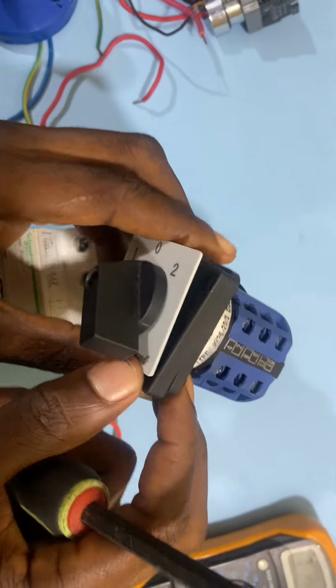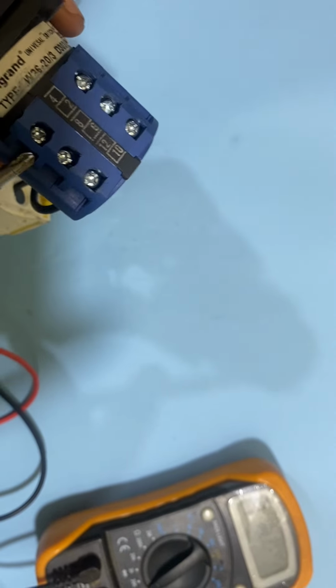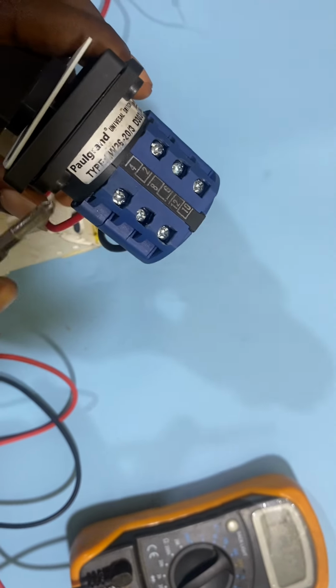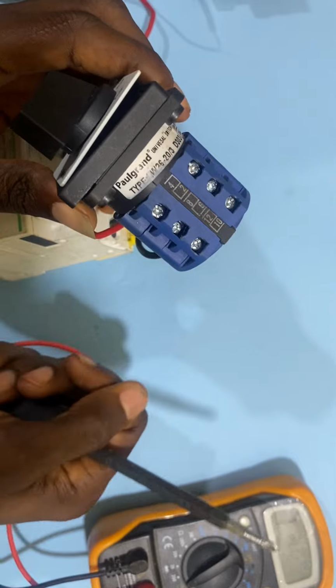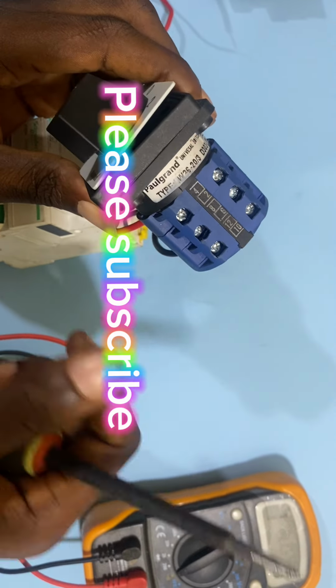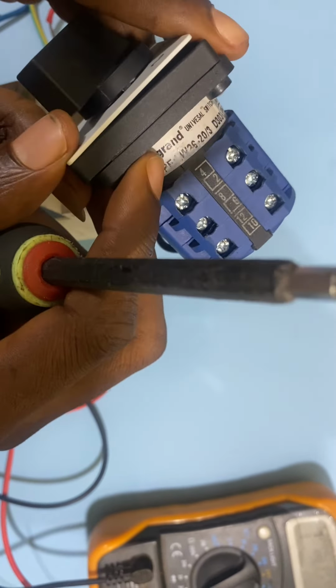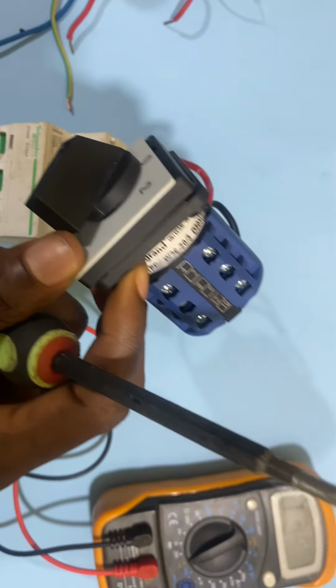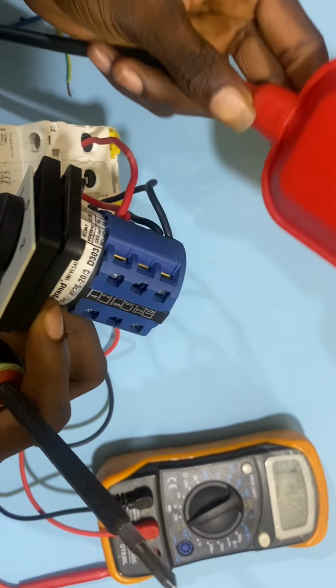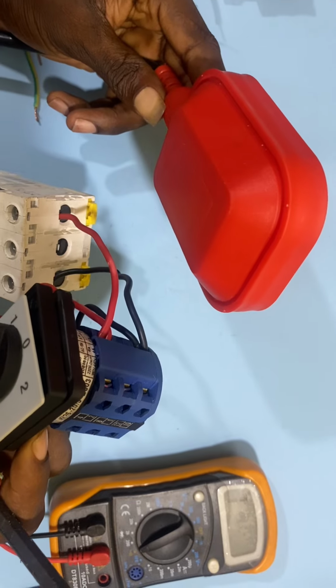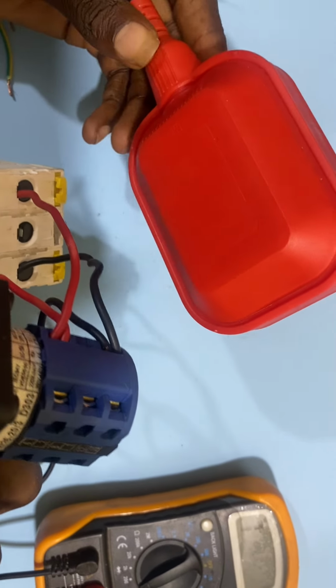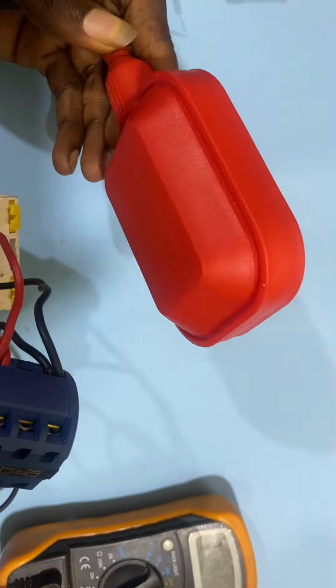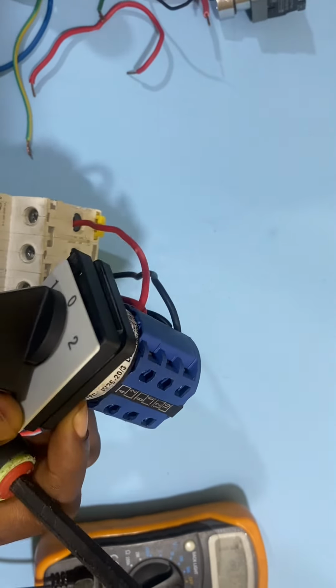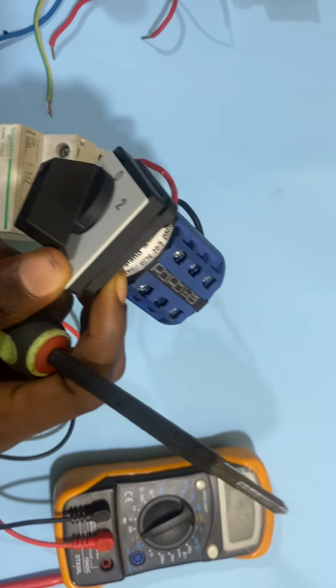And as I told you earlier, we are going to use a start and stop button to manually control the pump of water. When you press the start button, you manually pump the water, and you press the stop to stop pumping the water. We are also going to use a float switch to automatically pump the water. That is, when the water fills up the tank, the float switch will automatically stop pumping the water, and when there is no water in the tank, the float switch will automatically start pumping the water. So let's connect the start and stop button to the switch here.